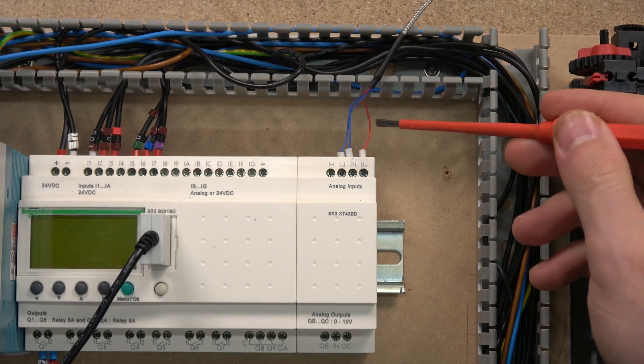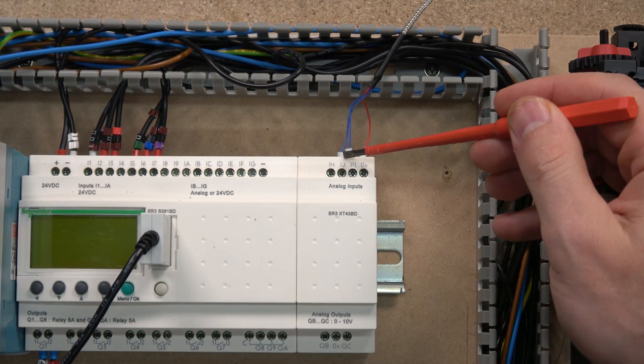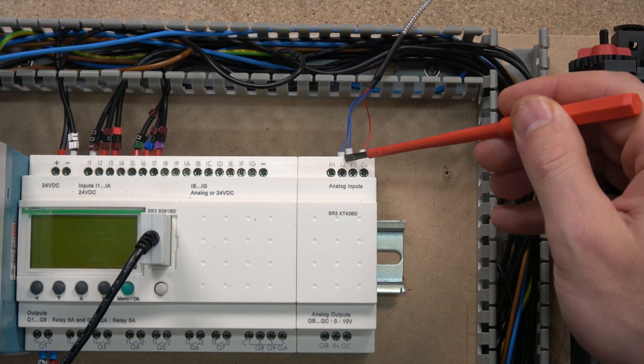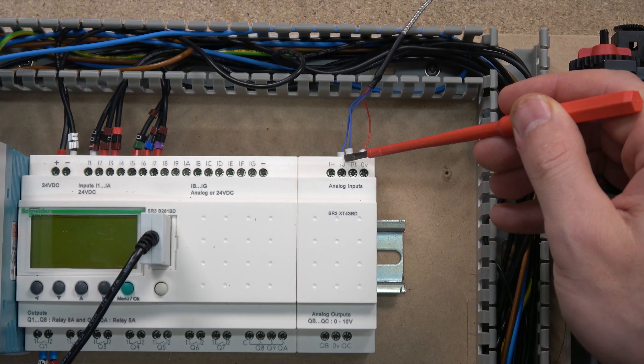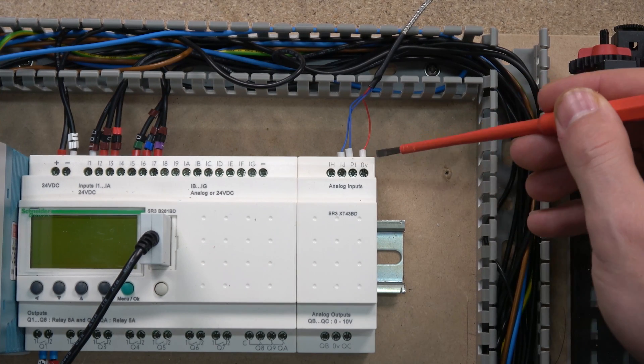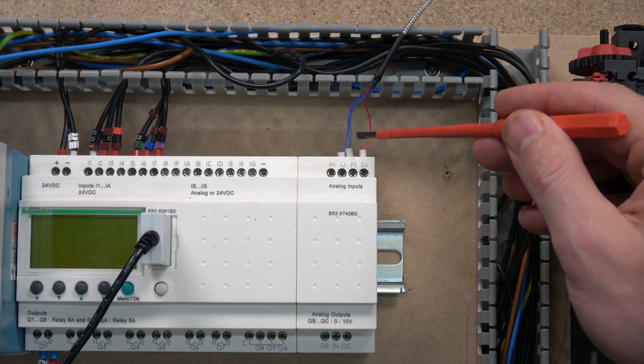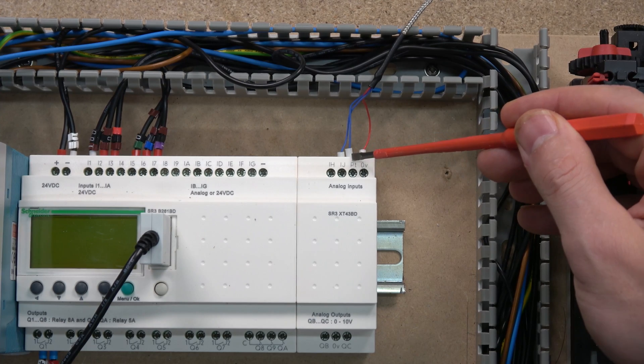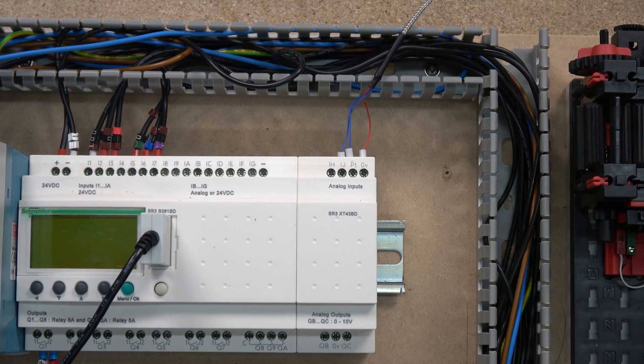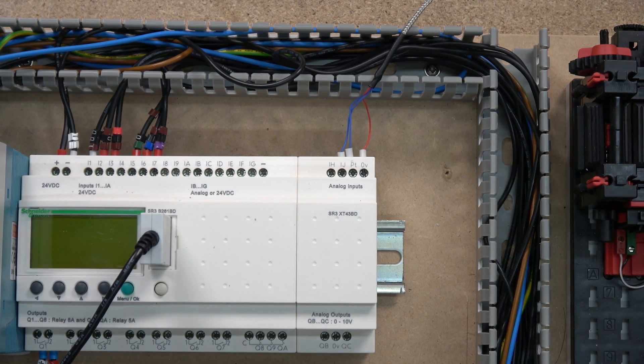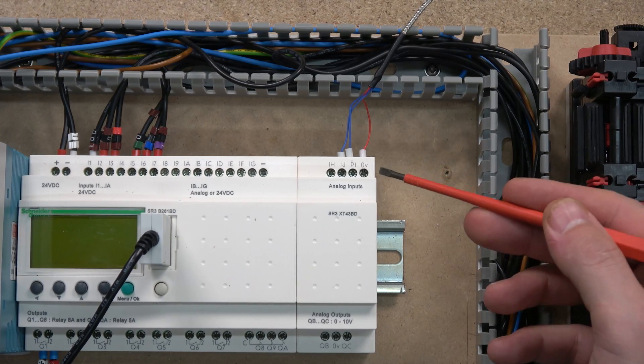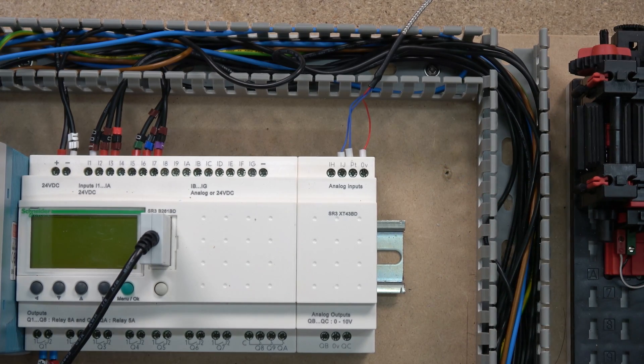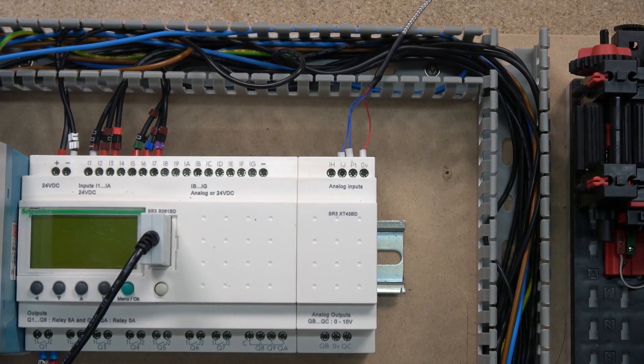As you can see down there, the channel we can use for a PT100 is IJ, and then the second same color ones goes in the PT, and the different color which in our case is red is going to go into zero. That's pretty much when it comes down to wiring.